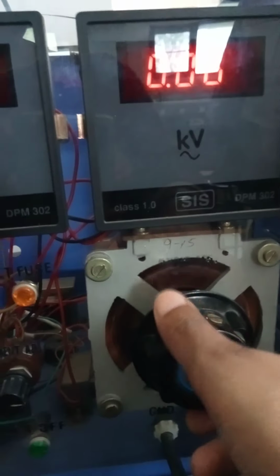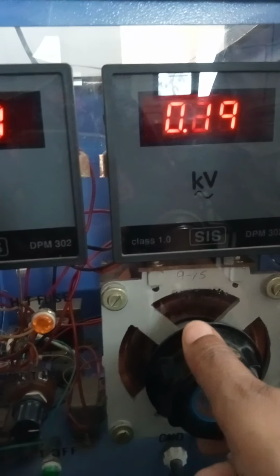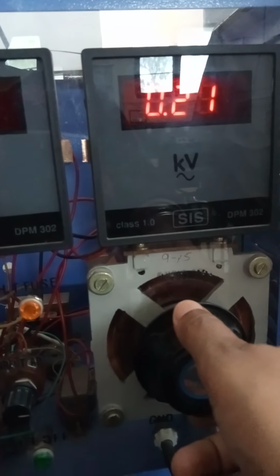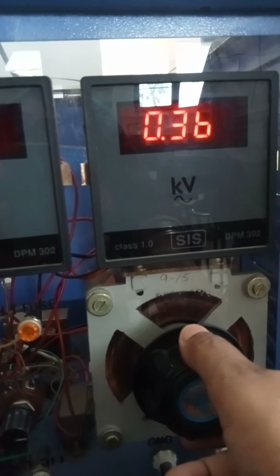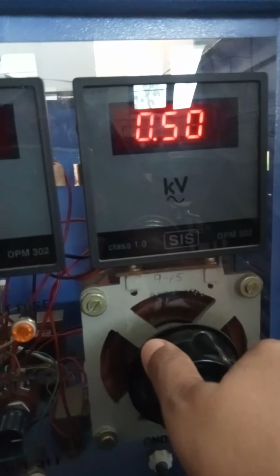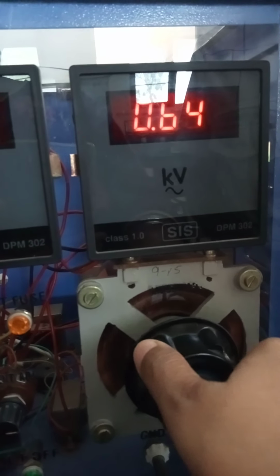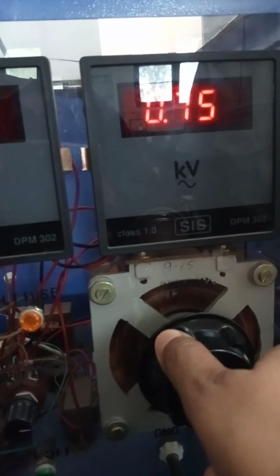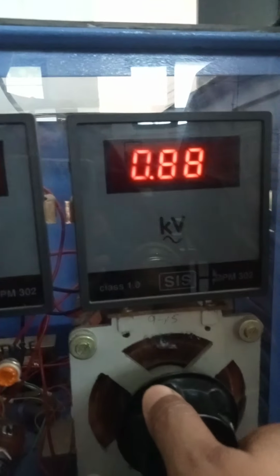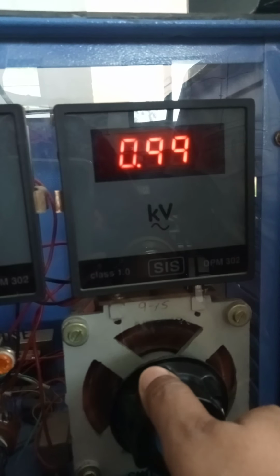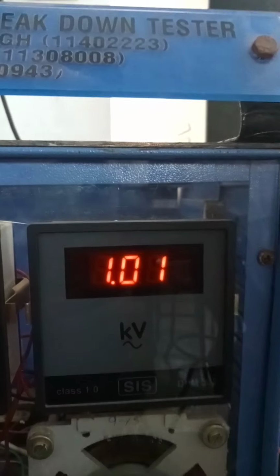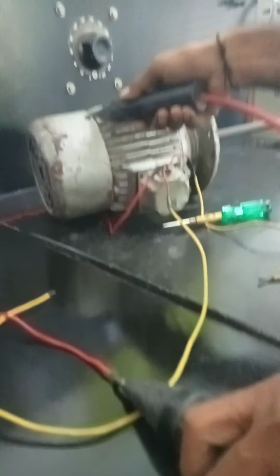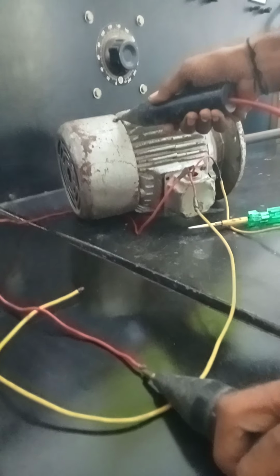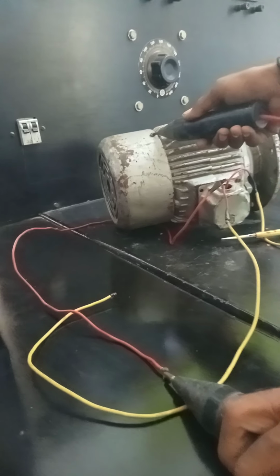Now I will increase the voltage slowly and steadily with the help of this variac to 1 kV. We will not give voltage over 1 kV because 1 kV is high voltage. If I give voltage beyond 1 kV, it may damage the motor also. So we will not give voltage beyond 1 kV. Now you can see I am rotating this variac and the voltage is increasing. So it is exactly 1 kV now, and I have connected one terminal with one phase and another with the body of the motor. Now as you can see, no buzzer sound is heard.